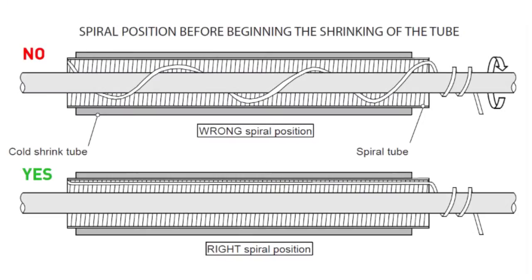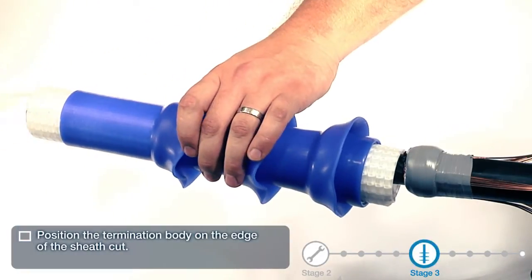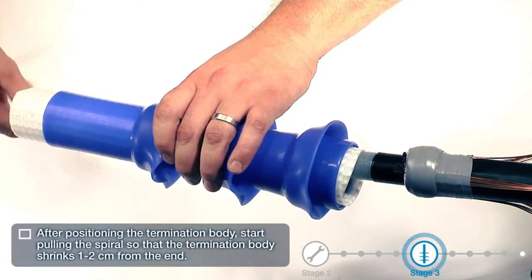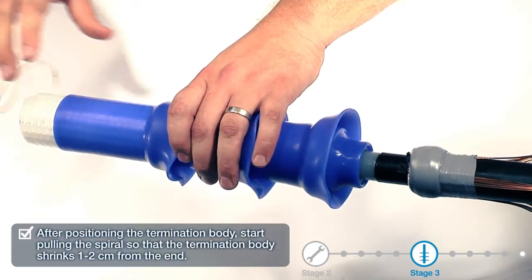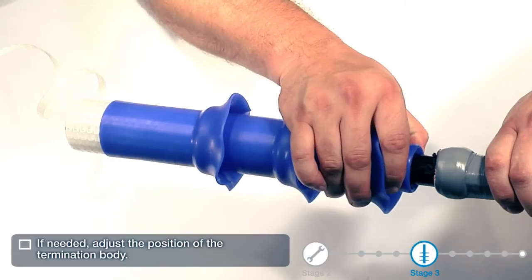Make sure that the spiral is positioned correctly before installing the termination. Position the termination body on the edge of the sheath cut. After positioning the termination body, start pulling the spiral so that the termination body shrinks 1-2cm from the end. If needed, adjust the position of the termination body.